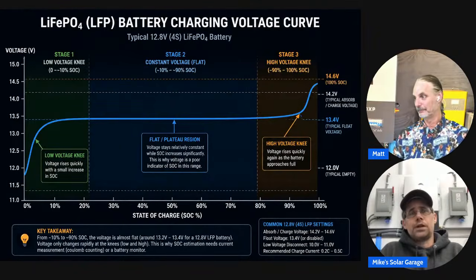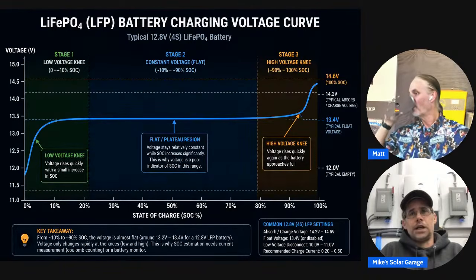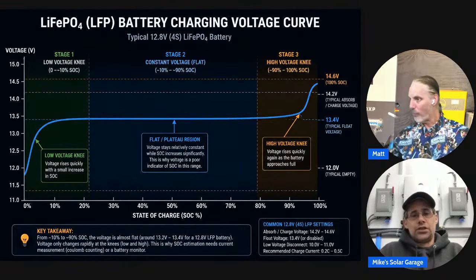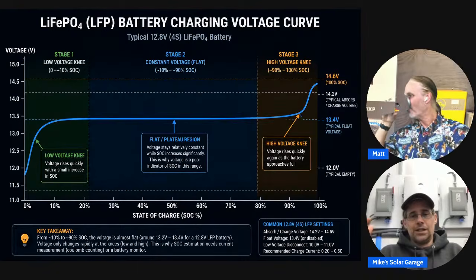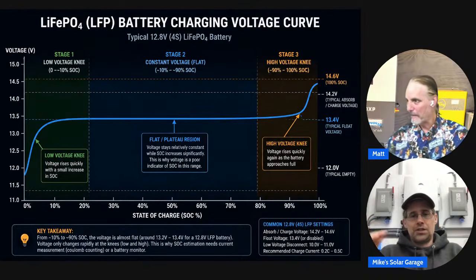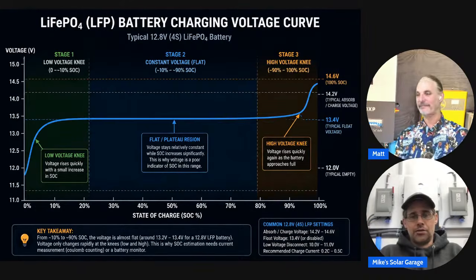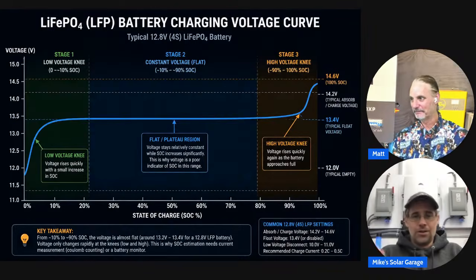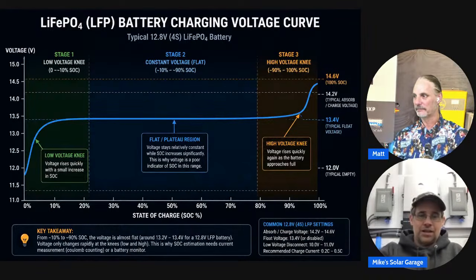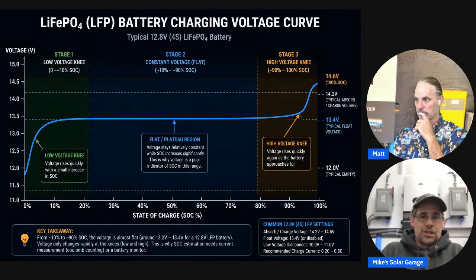Also, you can watch a battery charge and see it's at 85%, then within 20 minutes it hits 100, and you're like, wait a second, how is it at 100%? That's because you have one cell at the knee that just climbs up, hits a certain voltage, clicks off the charging, and says 'I'm full, we're at 100%,' because it's looking at the highest out of all the cells. So if they're out of balance, then it's all off.